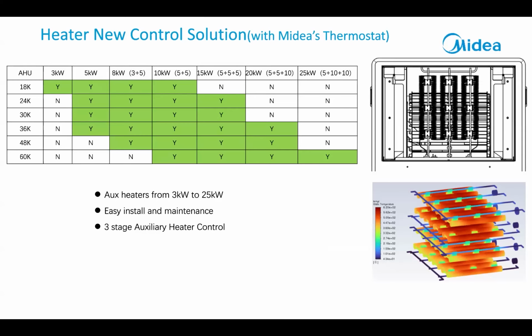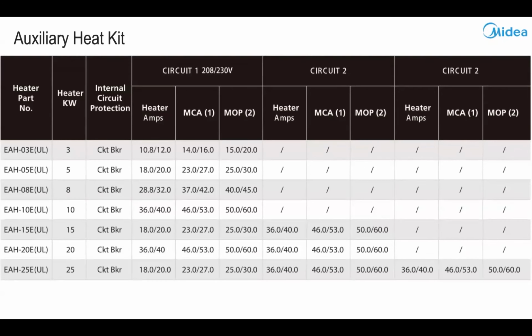Heater control. All right, so you have an option of 3, 5, 8, 10 kilowatts all the way out to 25 kilowatts. Your staging control runs across the top. 8 kilowatt and 10 kilowatt are two-stage. And then again, anything 15 kilowatt and above becomes three-stage heat for the auxiliary heat. Now, some of that's controlled internally. It is a two-piece heater. This table is your MCA and MOCP for your electric heaters. This is in the installation manual or the knee pad that comes with the unit.